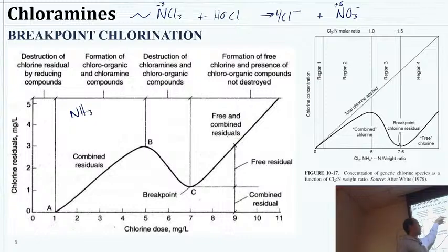So that's why our total chlorine residuals are dropping the more we add. It's kind of a bizarre thing to think about, but we add more chlorine, we get less chlorine. But that's the nature of what we're doing here. From then on, we break through this breakpoint spot, and now we are doing proper breakpoint chlorination. This is where the term breakpoint chlorination comes from.